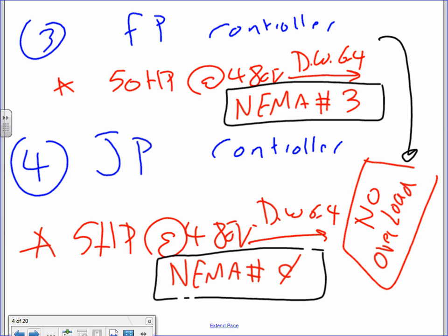So what they do is the code requires you not to have overload protection. Meaning if it gets overloaded and catches fire because of overload, let it be. You're already on fire. So you're just holding the ground until the firefighters come. So you're going to let it keep kicking that water where the fire is located. Does that make sense? No overload in it.